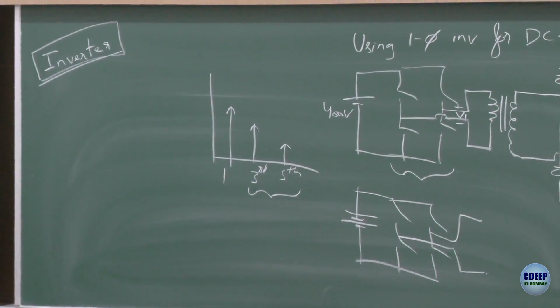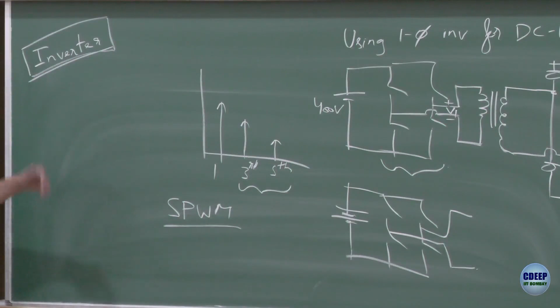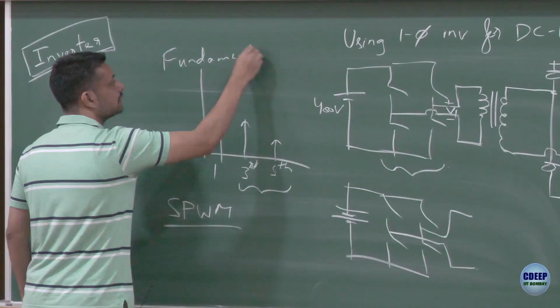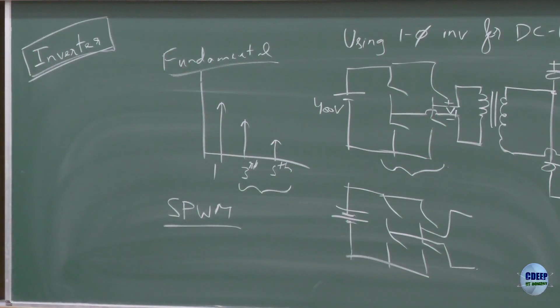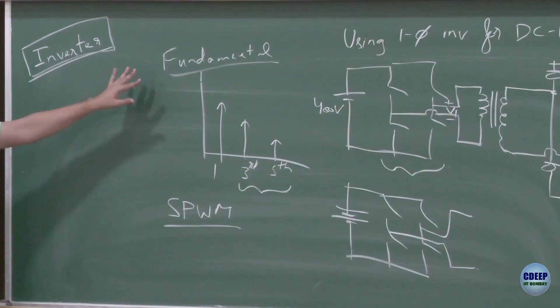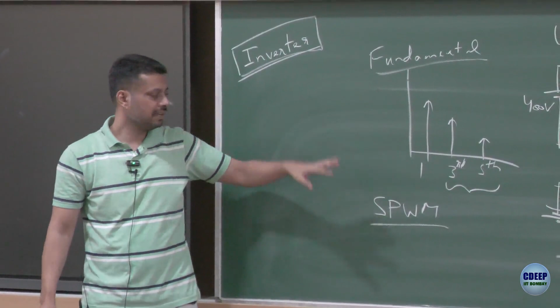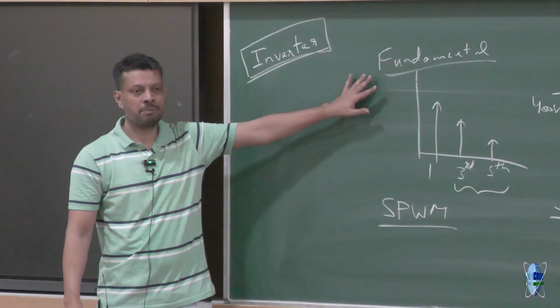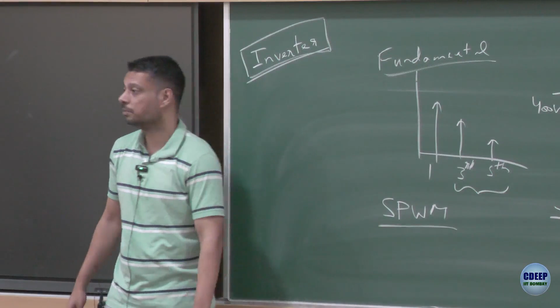SPWM stands for sine pulse width modulation. With SPWM you would not hear that sound, but with fundamental modulation, switching once every 50 hertz, you have low frequency components and you would hear it. Fundamental modulation is generally cheaper to implement, so for house use, such a sophisticated scheme isn't always required. Some manufacturers use fundamental modulation since it's easier to implement, while others use sine triangle PWM, in which case you won't notice much difference running a fan with it.